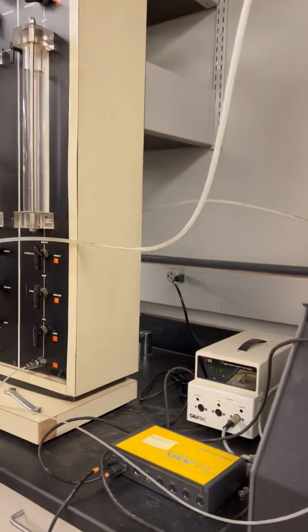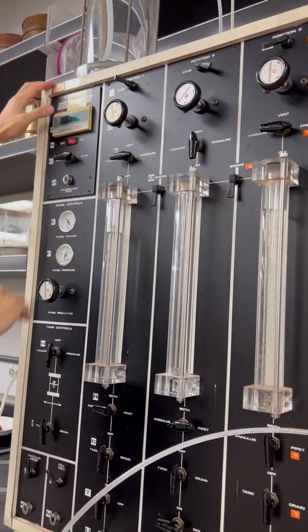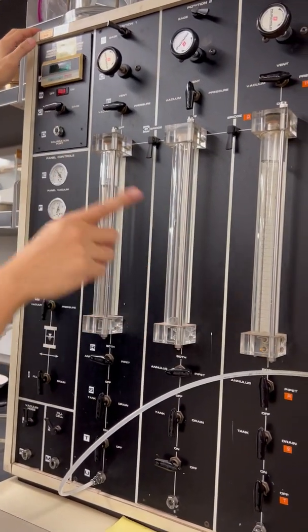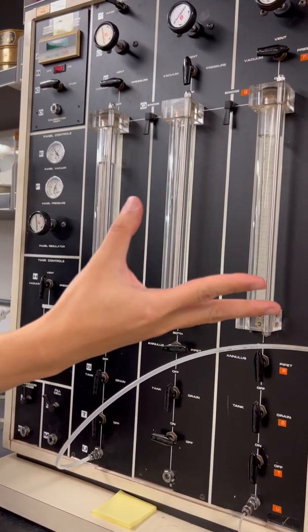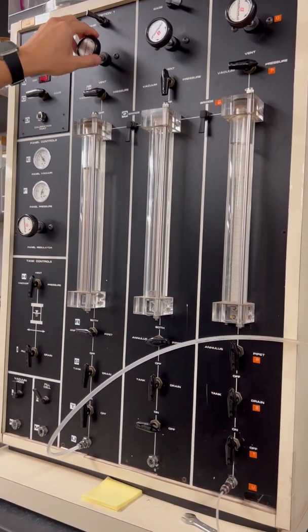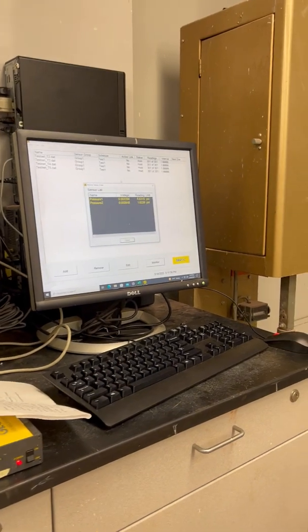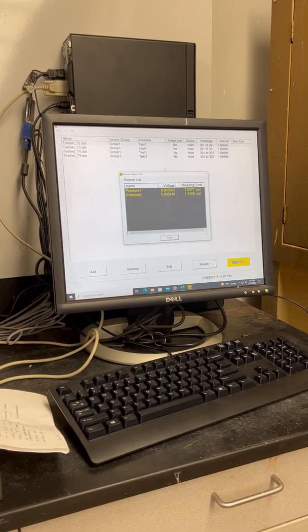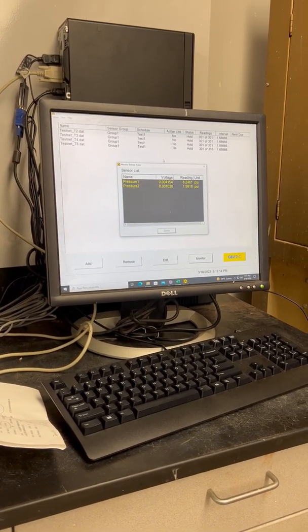Now we want to change our cell pressure from five to ten. We pull our sensors and increase the cell pressure — we can also read it from the panel. By the way, those two gauges have not been calibrated, so I'm using the sensor as a reference. If they were well calibrated they should agree; right now they're slightly different. I'll keep my eyes on the reading until we reach 10 psi on the cell pressure.